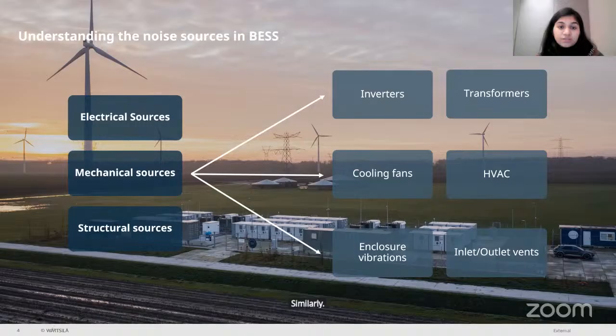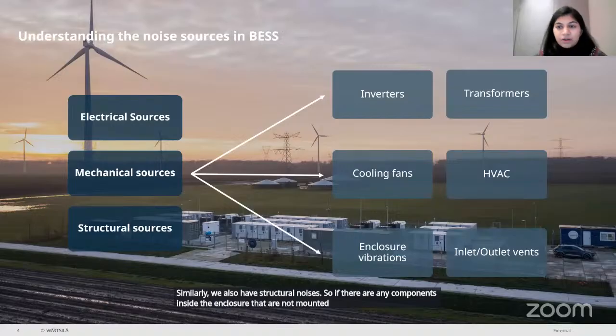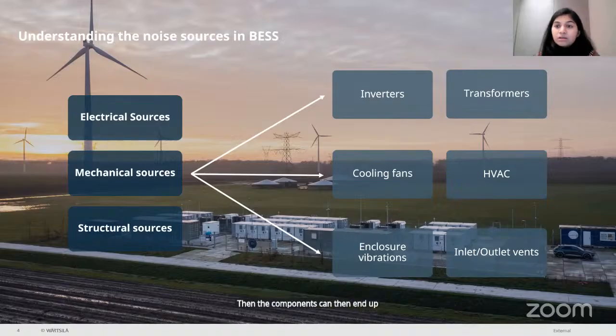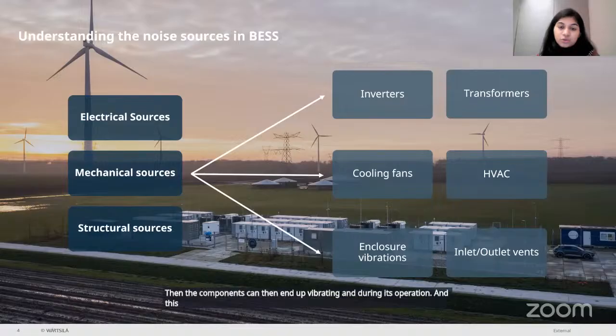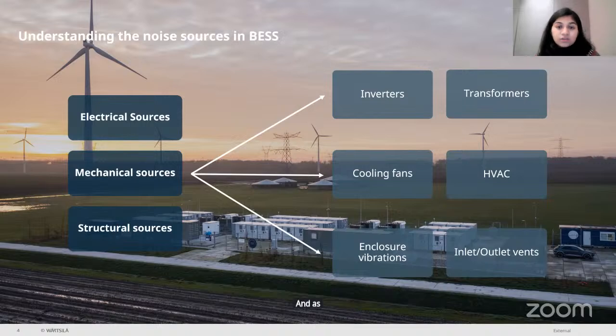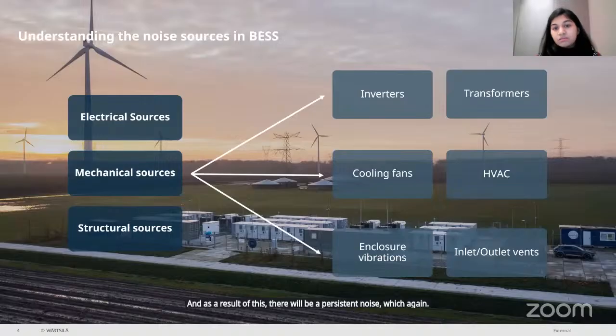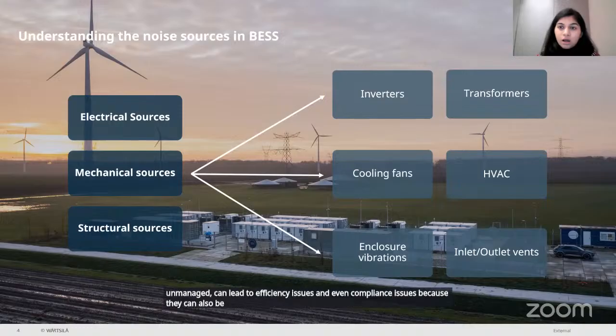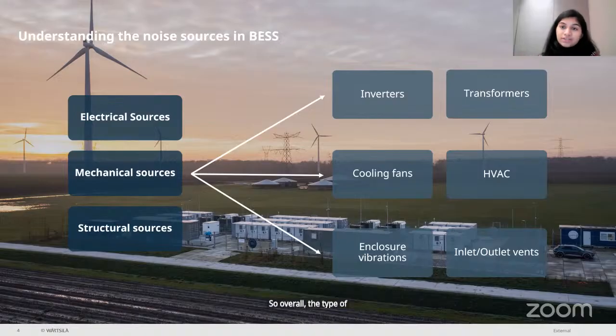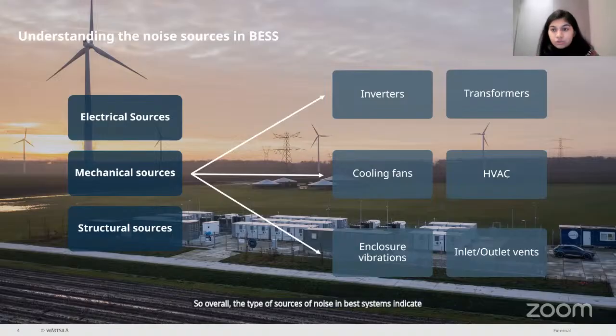Similarly, we also have structural noises. If there are any components inside the enclosure that are not mounted properly, or any loosely placed equipment, then the components can end up vibrating during operation, and this vibration translates into what is known as vibroacoustic noise, or noise that generates from vibrations. As a result, there will be a persistent noise, which if unmanaged can lead to efficiency issues and even compliance issues, because it can be quite audible and quite dominant as well. So overall, the types of noise sources in BESS systems indicate how exactly we need to tackle the noise topic.